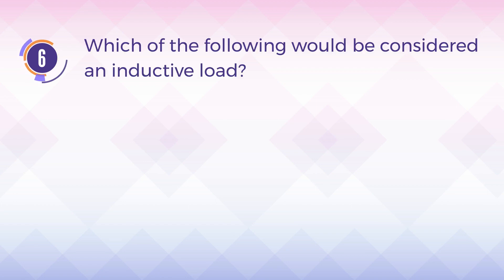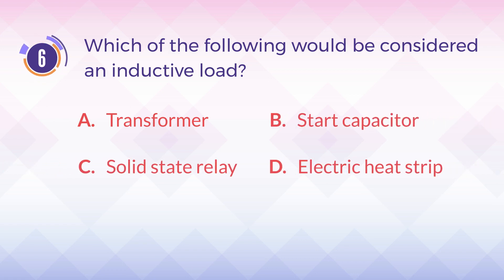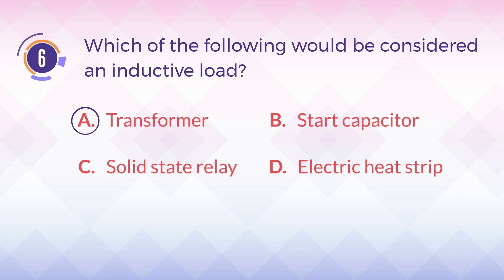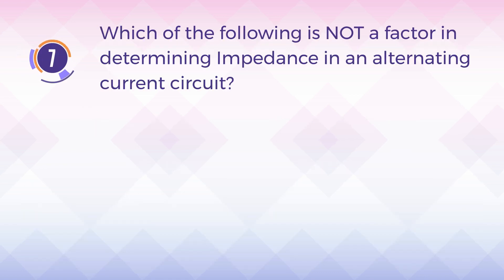Number six: which of the following would be considered an inductive load? A) transformer, B) start capacitor, C) solid state relay, D) electric heat strip. The correct answer is A) transformer. Explanation: an inductive load is a load consisting of a coil of wire which will cause current to lag voltage, such as a motor or transformer.